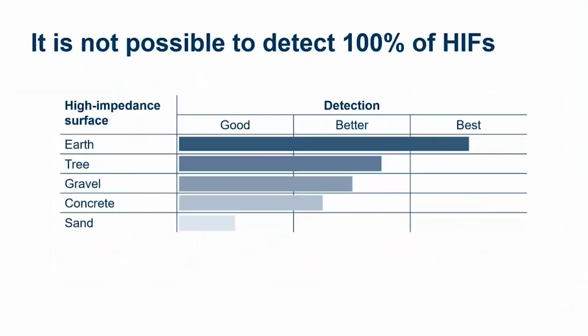Now, we talked about AST and how it works. I don't want to give the impression that this is going to be able to detect 100% of high impedance faults. I'm not aware of a current-based detection system that can detect 100% of high impedance faults on a 4-wire multi-grounded system. In this case, remember, we're using current. We're looking at the harmonic signature of current. In some cases, if we have a conductor laying on, say, dry sand or dry asphalt, we may have little to no current whatsoever, and in that case we're not going to be able to detect it using AST. So our sensitivity and our ability to detect a fault is going to really depend on what surface our conductor is laying on and how much current we have. What's the available fault current? It's important to keep that in mind.